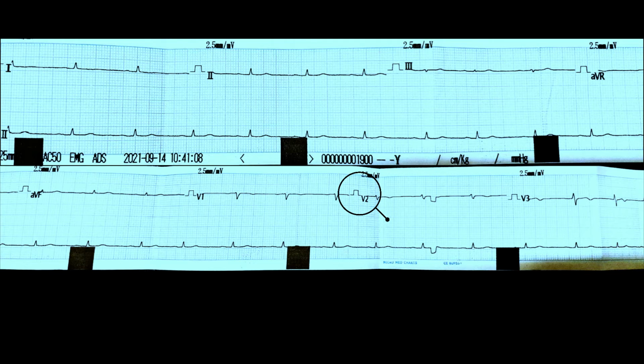If the calibration is not accurate, then in the ECG you will get a false R wave or a false S wave. So it is very important that your ECG machine has to be calibrated, the paper has to be calibrated, and then you look at the complexes in lead 1 to AVF, V1 to V6. So it's always like that. And if you are not provided with the calibration of the ECG, you may ask for the calibration, because the amplitude of the R wave will depend on the calibration.